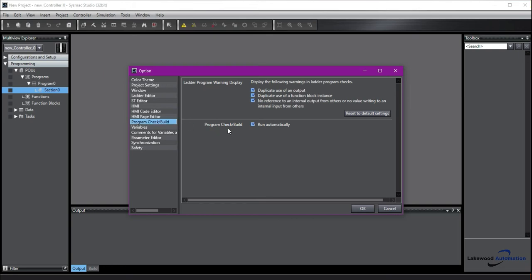Now, the Program Check Build is something that bothers some people because if you go in your ladder editor and you add a coil, you'll notice that before you get that variable name in there, you'll get a red exclamation point under your program. And that just means it is constantly checking and building your program for errors. This can save you a lot of time because it's happening in the background constantly. So whenever you are ready to go online, your program is probably already built.